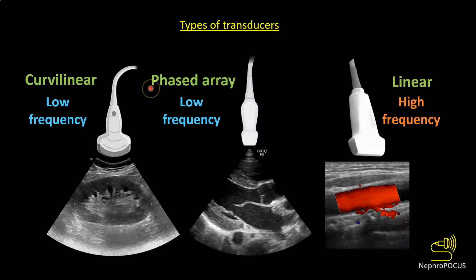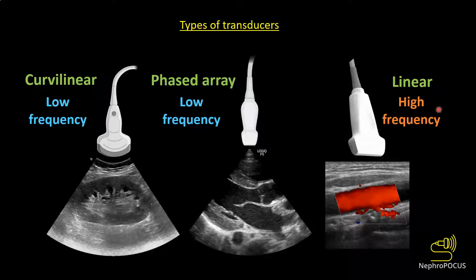Both curvilinear and phased array probes are low-frequency probes. The lower the frequency, the deeper the ultrasound beam can penetrate, but at the expense of resolution. Linear probes are high-frequency probes which offer better resolution but cannot penetrate as deeply, so they are used to image superficial structures such as AV fistulas or to guide dialysis catheter placement.